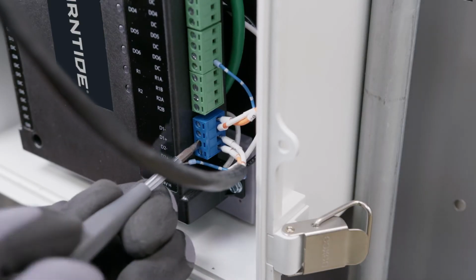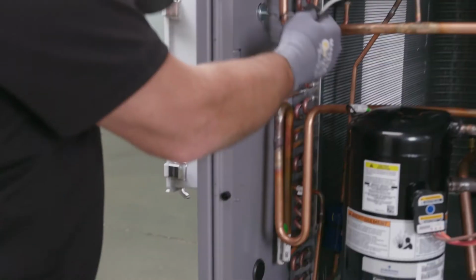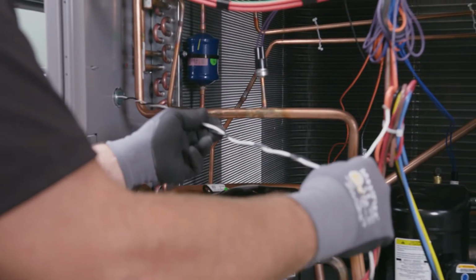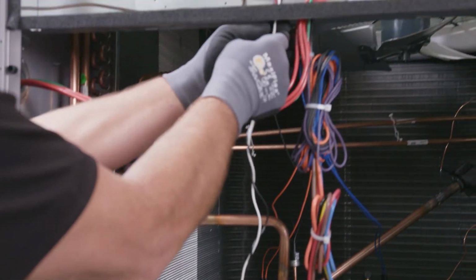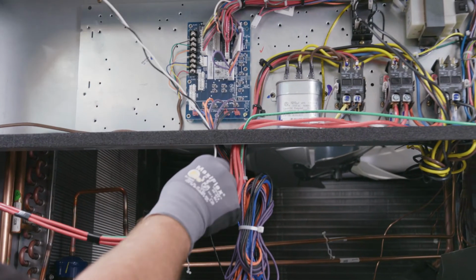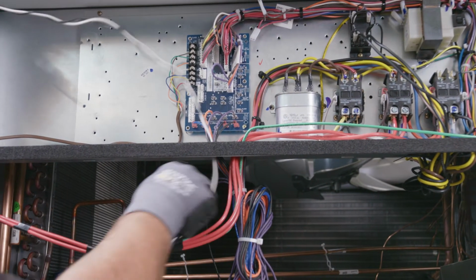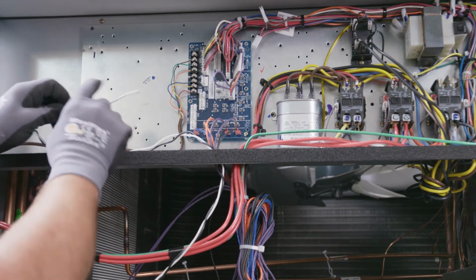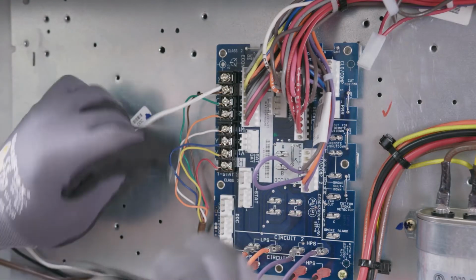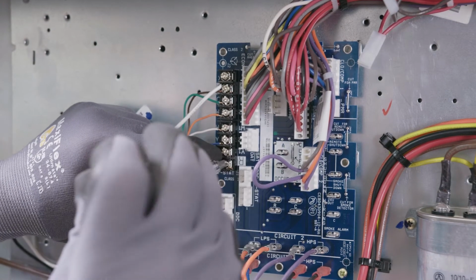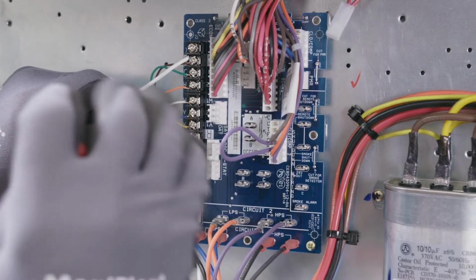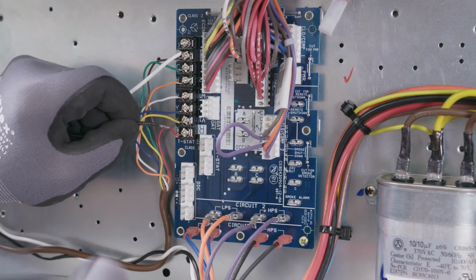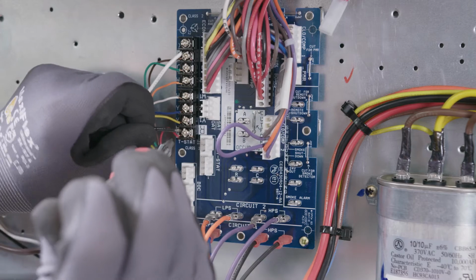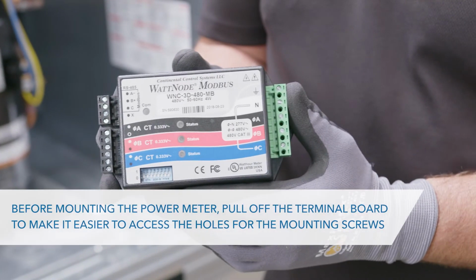Now that you've got the panel mounted, you want to pull out the black and white wires, which is the 24-volt power supply to the panel. Simply run the black and white wires to the unit transformer or to the terminal block on the unit. Once you've run the 24-volt power supply for the weatherproof enclosure panel to the unit, simply terminate it on the C and the R terminals to power up the panel. Now you're ready to install the power meter.